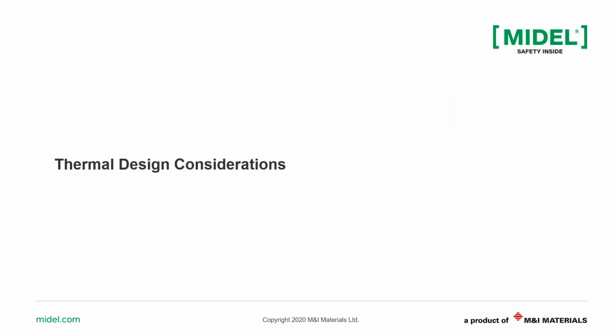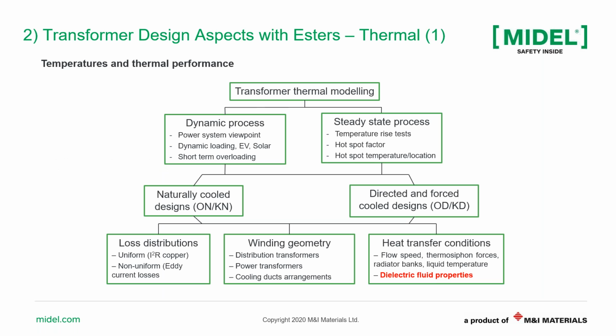Now let's talk a little bit more about the thermal, because we know esters have different viscosity than mineral oil, and so they can contribute to higher temperatures. And so I thought to share some basics here. To assess the transformer thermal modeling or performance, usually we can look at either the steady state processes or the dynamic processes. When we talk about the steady state processes, this is the temperature rise test in the factory after we design the transformer to derive a hotspot factor, which helps us in estimating the hotspot temperature, which is the critical temperature in a transformer winding when the transformer starts accelerated aging.